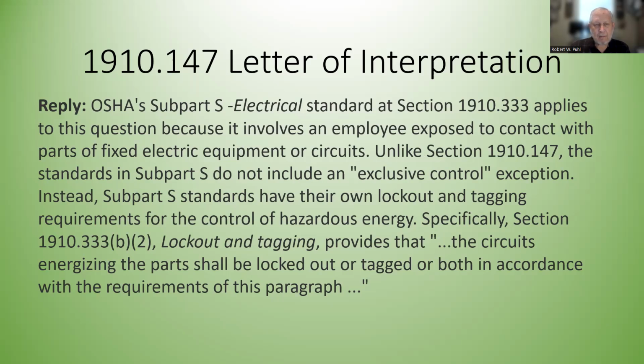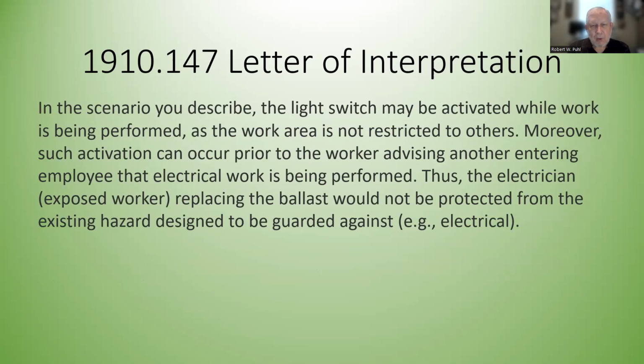In the scenario described, the light switch may be activated while work is being performed, as the work area is not restricted to others. Moreover, such an activation can occur prior to the worker advising another entering employee that electrical work is being performed. Thus, the electrician, the exposed worker replacing the ballast, would not be protected from the existing hazard designed to be guarded against electrical. So a couple of things happened in this one.